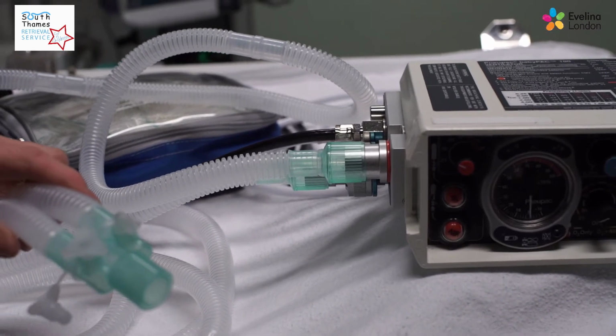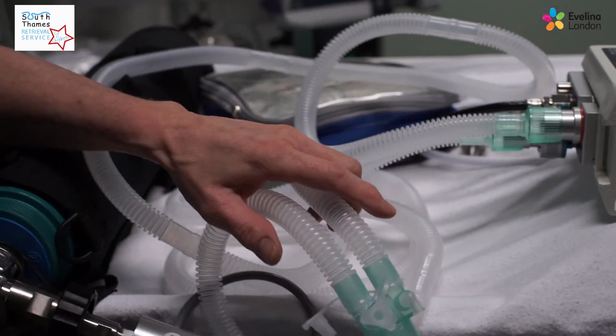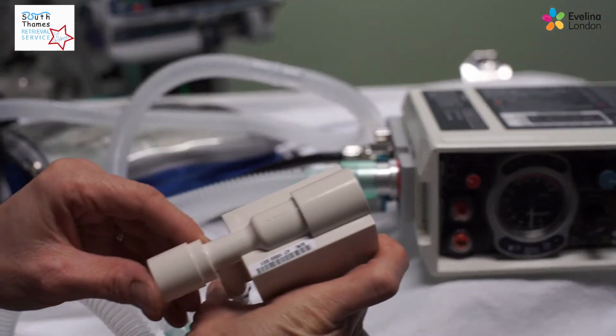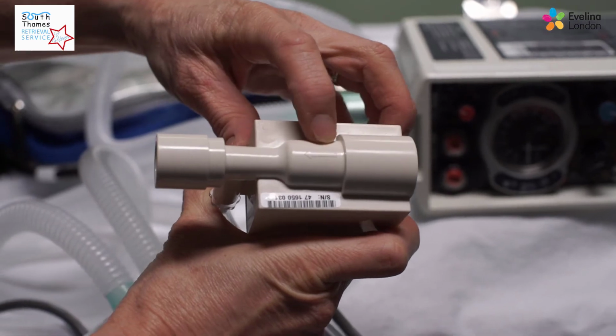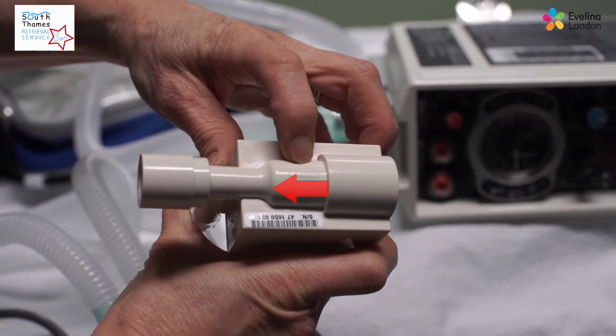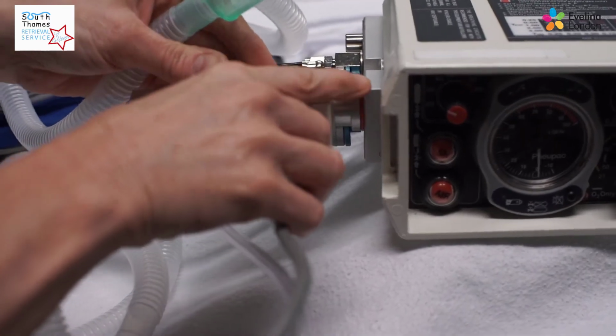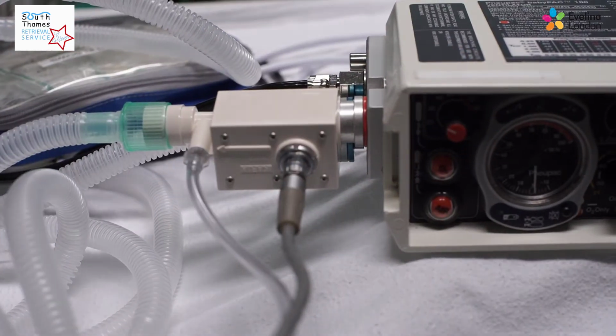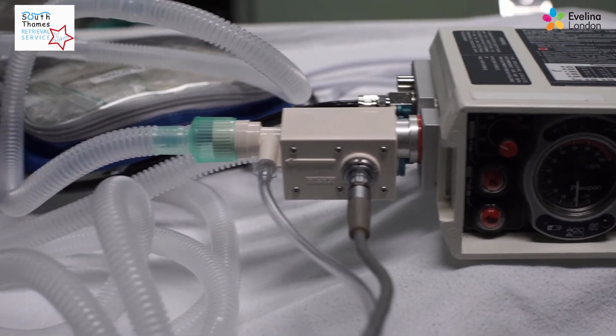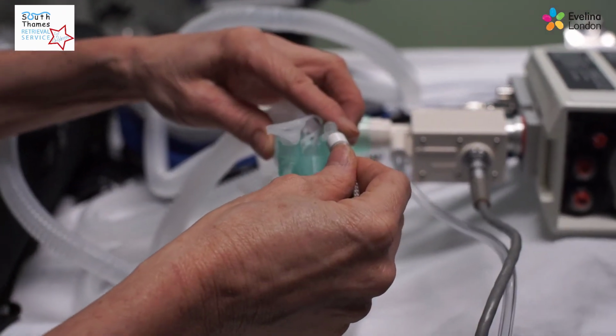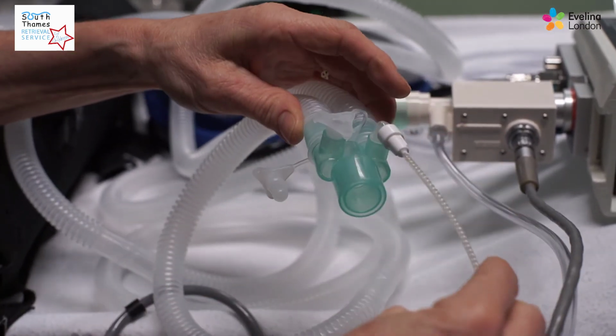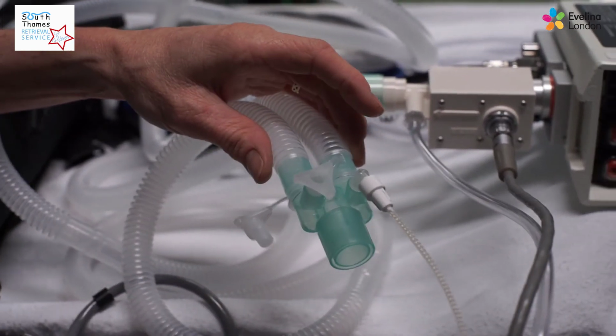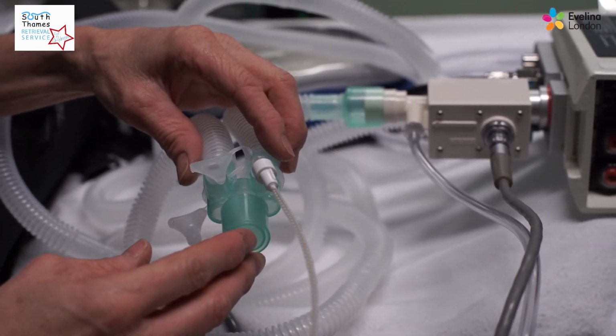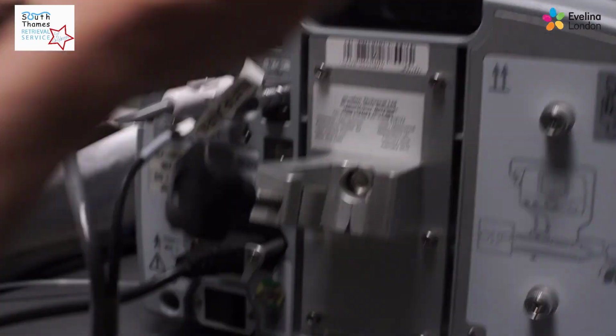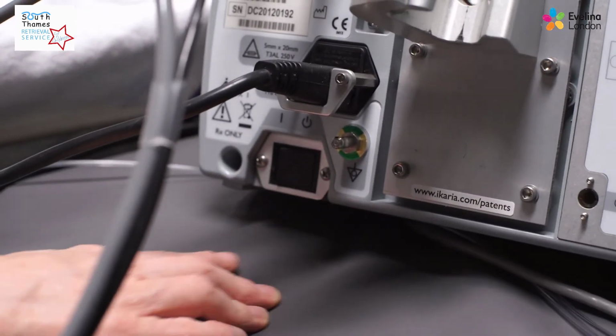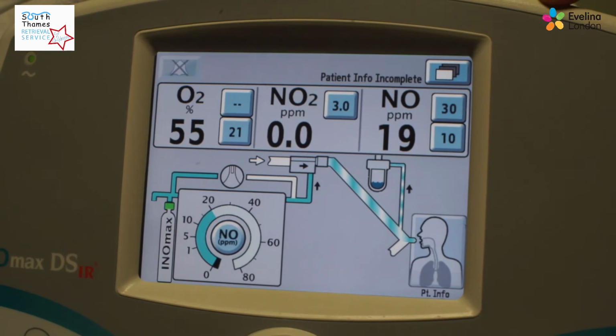From here, you can then connect the inject block, which is a cream block, to the outflow port of the portable ventilator, the baby pack, with the arrow going towards the patient. You then need to connect the sampling line from the monitor to the ventilator circuit using the clear elbow. You're then ready to turn your nitric on and your Inomax monitor on. To do this, there's a black button at the bottom of the monitor. So now your nitric is all ready and set up to use.